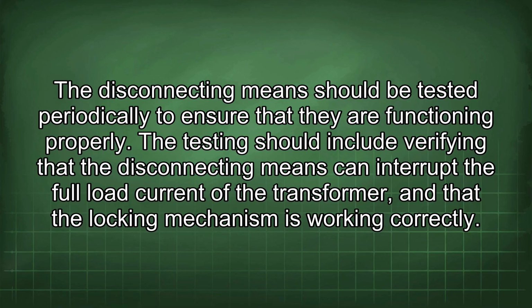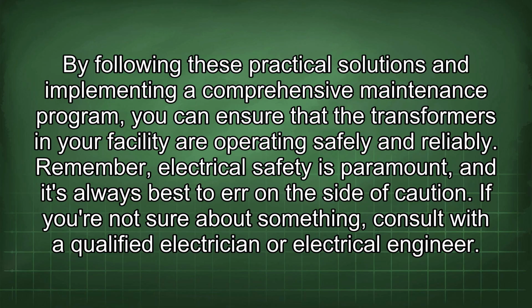The testing should include verifying that the disconnecting means can interrupt the full load current of the transformer, and that the locking mechanism is working correctly. By following these practical solutions and implementing a comprehensive maintenance program, you can ensure that the transformers in your facility are operating safely and reliably.